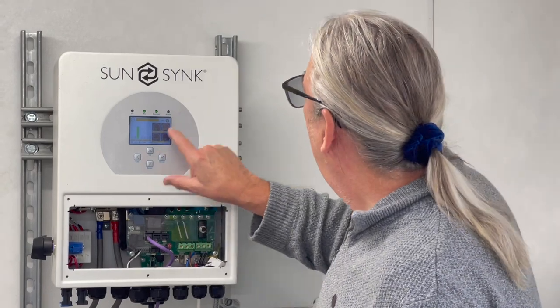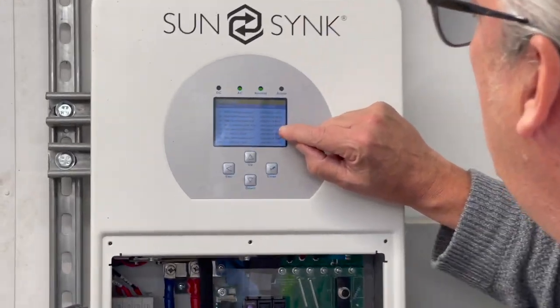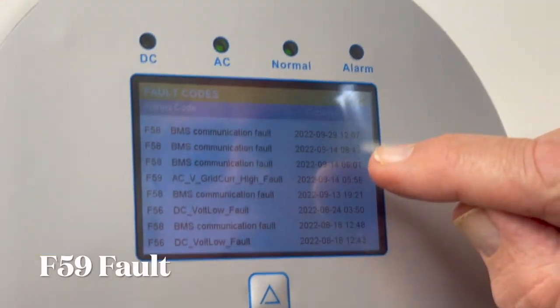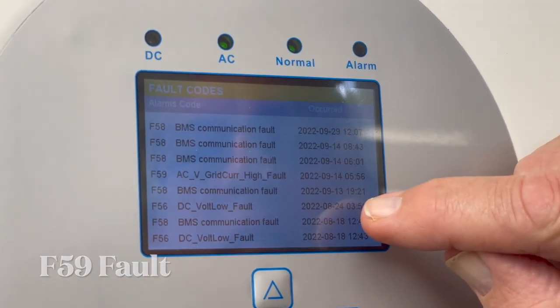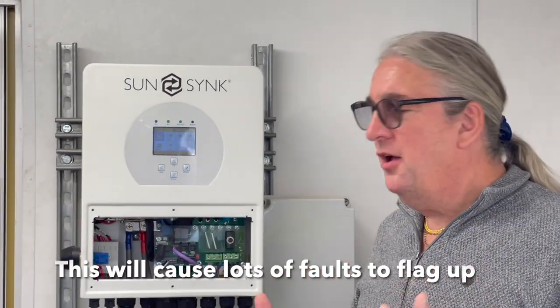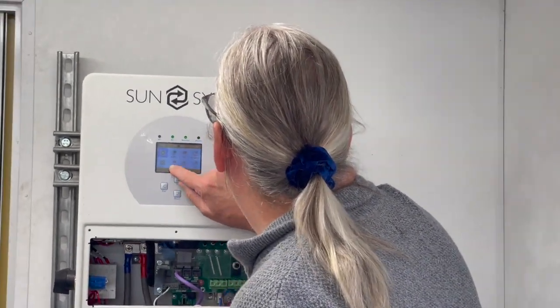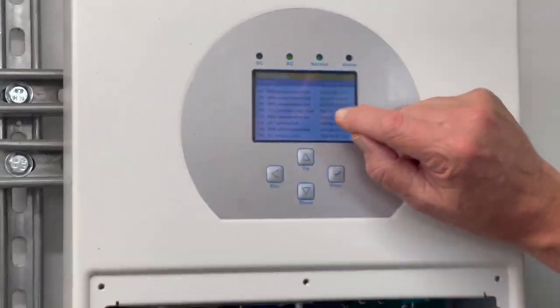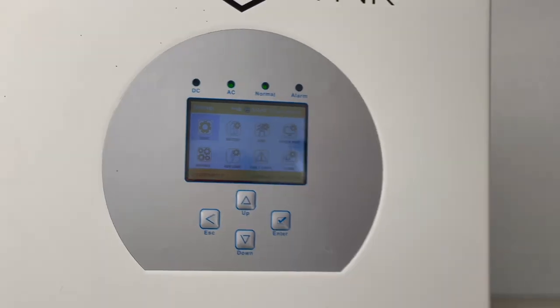This particular site had a problem - it wasn't working when I got here. If I go into fault codes, you'll see voltage. Obviously you'll see lots of BMS not communicating and DC supply. This one here is actually an overload situation - they've obviously overloaded it. So going back: AC voltage grid current high. So it's a grid current overload on the grid current.